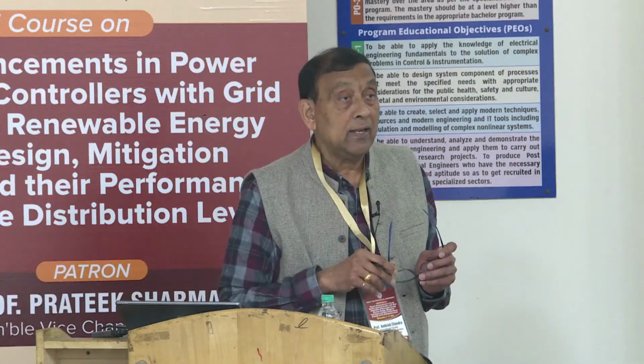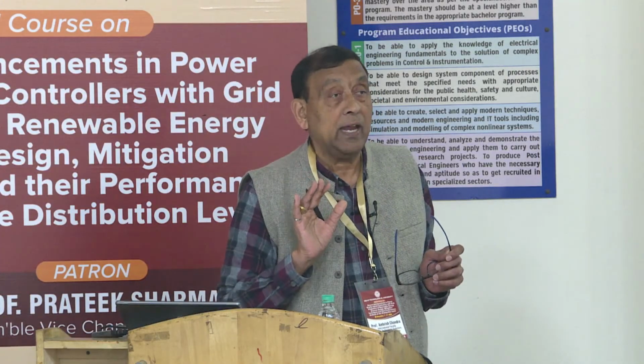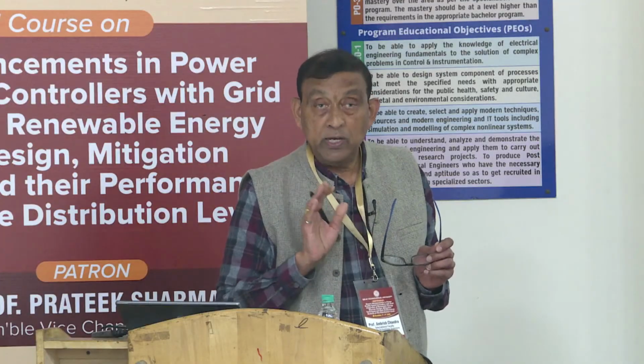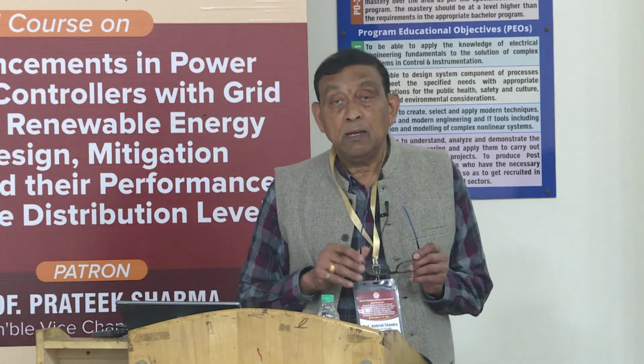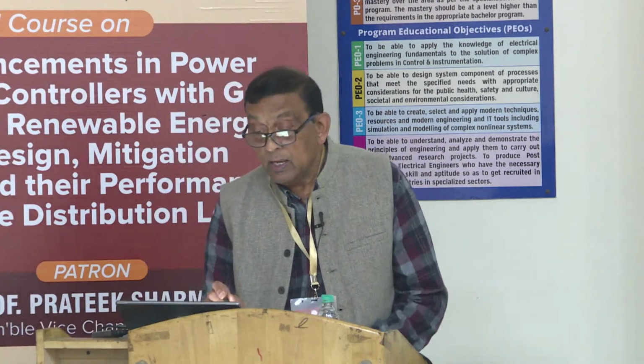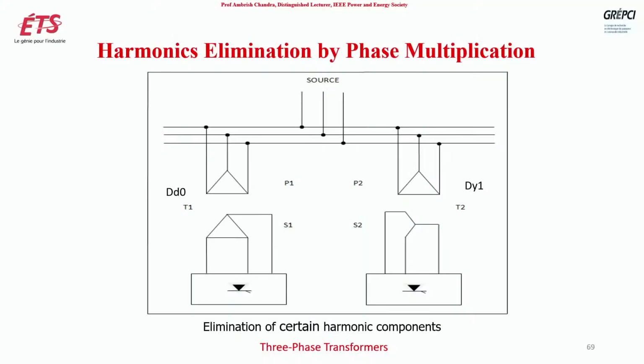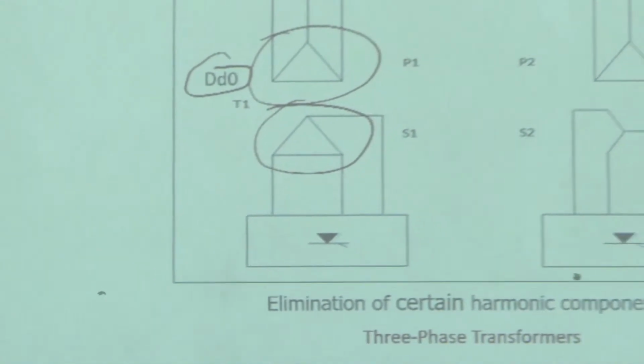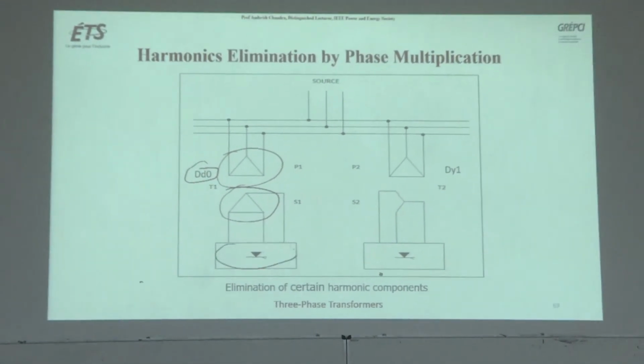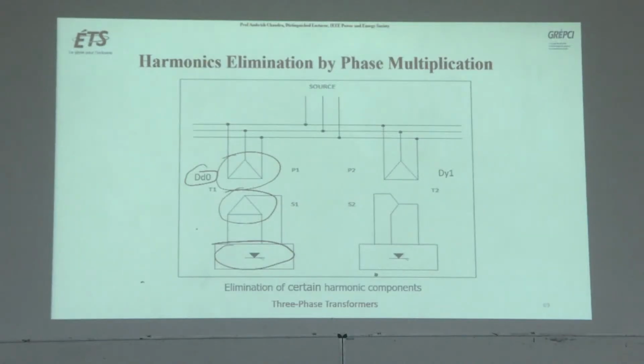And I told you that this is the worst decision an electrical engineer can take. So he has to be very careful to think about this. What is the harmonic situation? Suppose we have a DD0 transformer here, delta in the primary, delta in the secondary, and 0 degree phase shift. Now you have non-linear load here. So 5th harmonic and 7th harmonic are generated here, which will be transferred here, I5, I7, which will go here, I5, I7 in all the three phases, A, B, C.